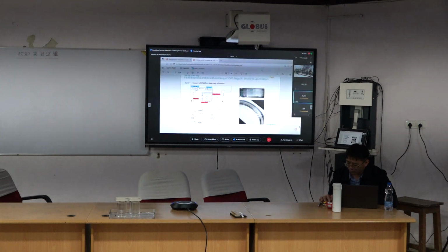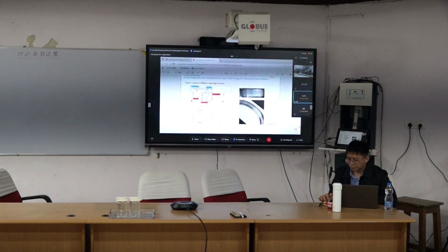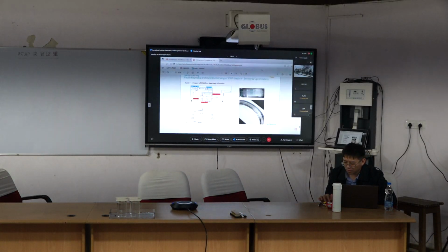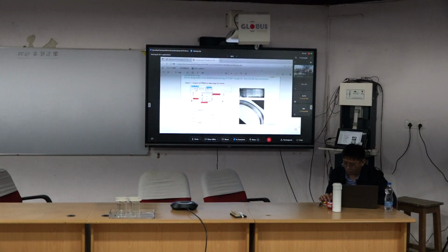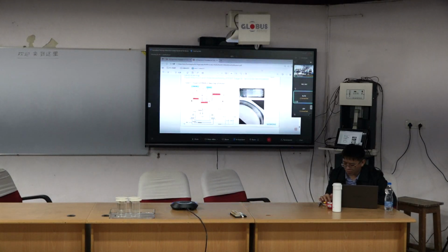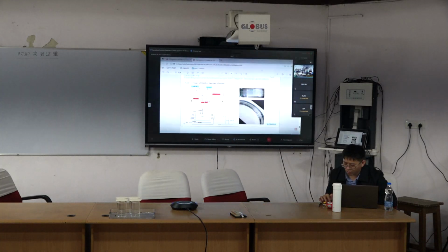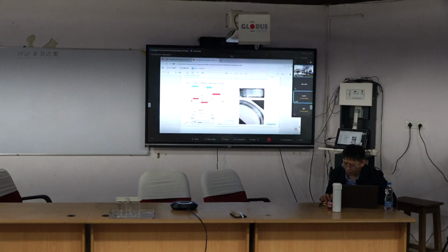If the insulation capacity of the lubricating film on the motor bearing cannot withstand this shaft voltage, a circular current flows through the circuit: shaft, bearing, motor housing, bearing at the non-drive end and drive end, and shaft. This is for the larger frame size motor.